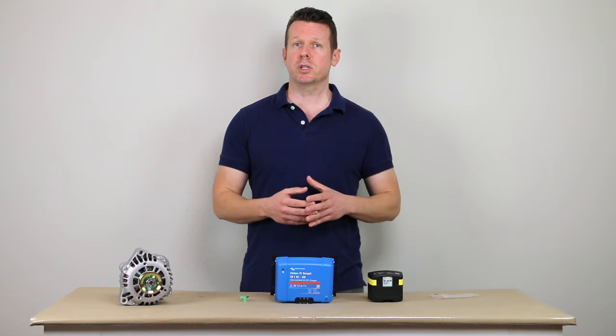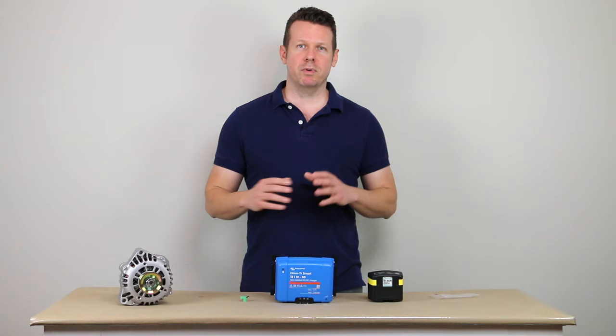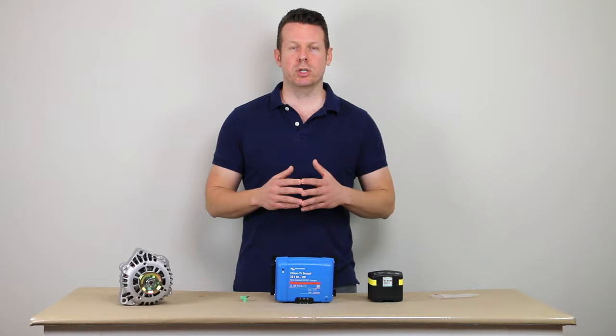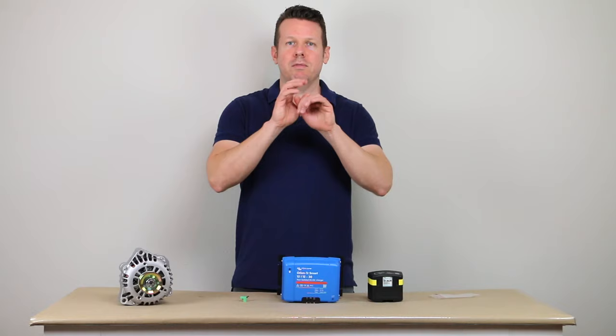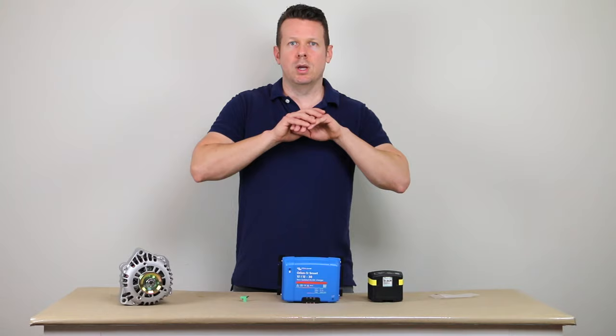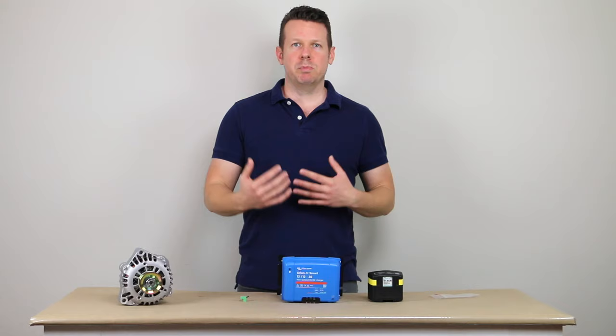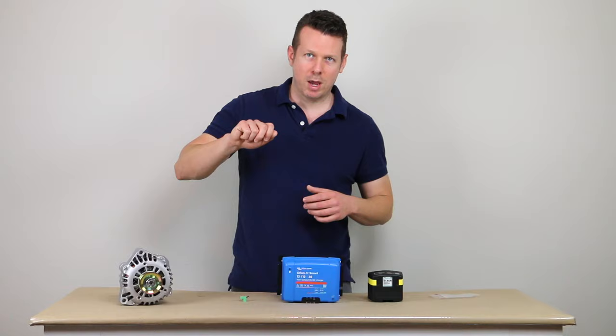So mistake number three, I'm going to talk about two different mistakes here that have to do with wires heating up due to a poor connection. So the screw terminals here at the bottom of the charger, I noticed last week, I did a system and I tightened those screw terminals and it kind of takes the strands of the welding cable. This would be six gauge welding cable going in this unit. And it spreads them out and kind of flattens them out. And I guess there was some adjustment, but I came back 24 hours later and my connection was loose. And I went ahead and re-tightened it.